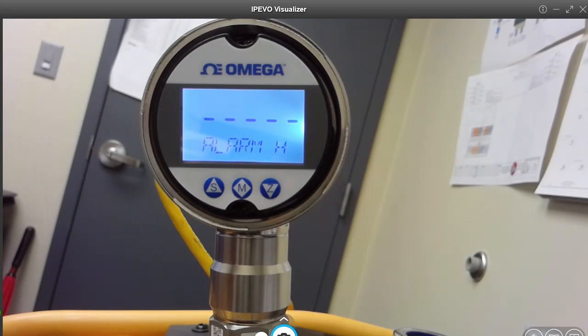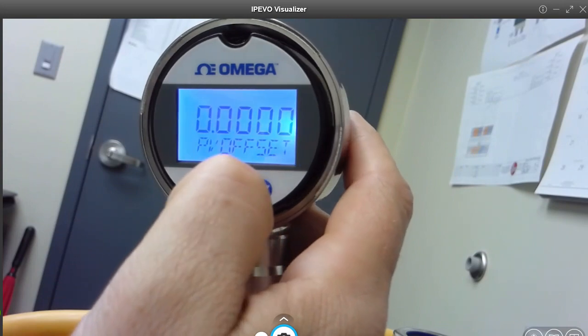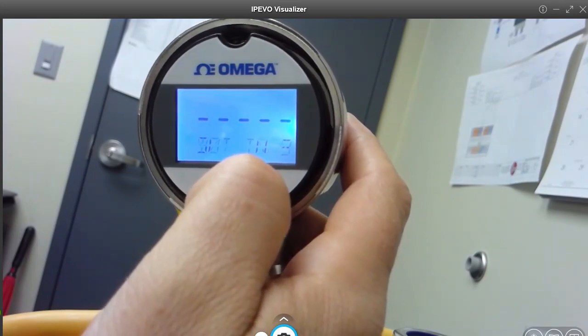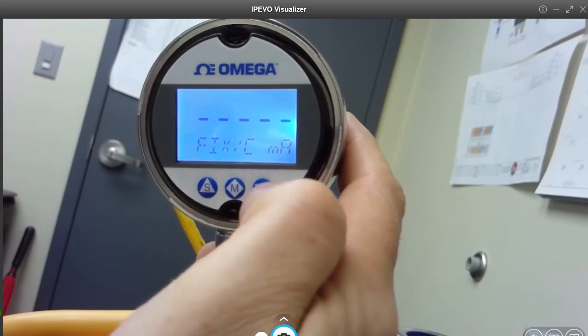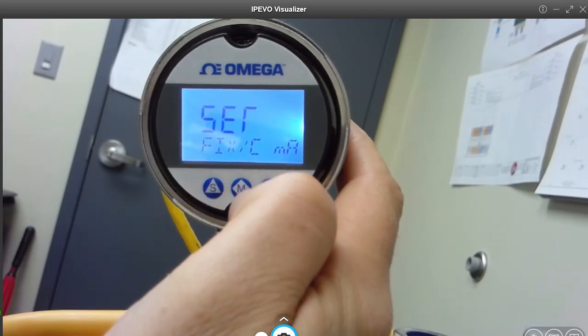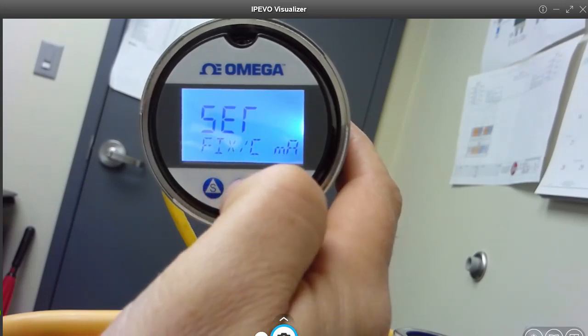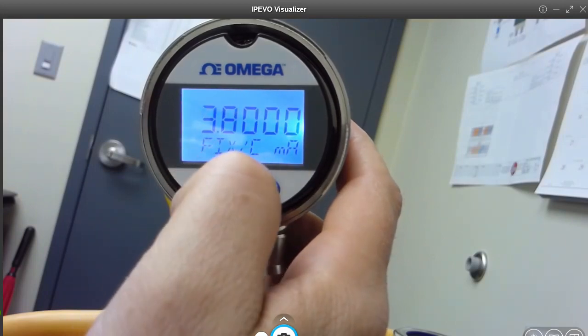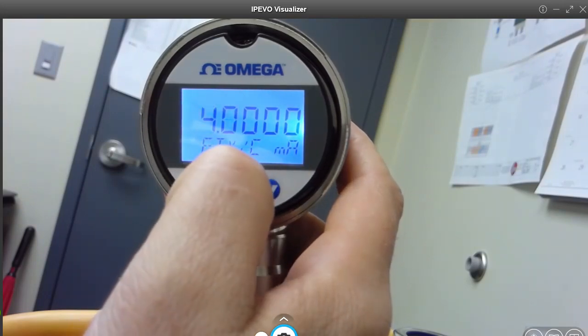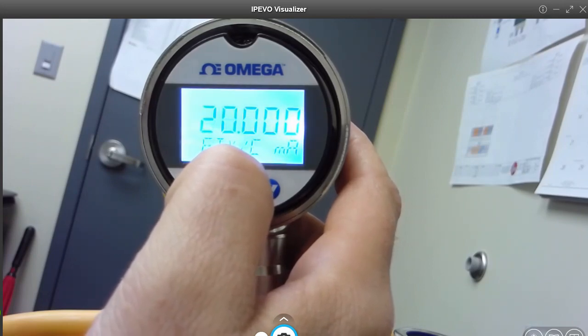Next, we're going to send our high and low signals. We don't want to offset. We're not using any pole addressing. No. We're going to set a fixed milliamp output. So we can hit this button here and keep incrementing it. It has presets. So there's 4. There's our low. What we're concerned with is 20. So we're going to set that to 20 milliamps.